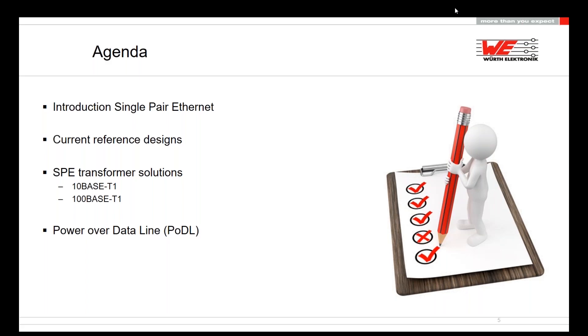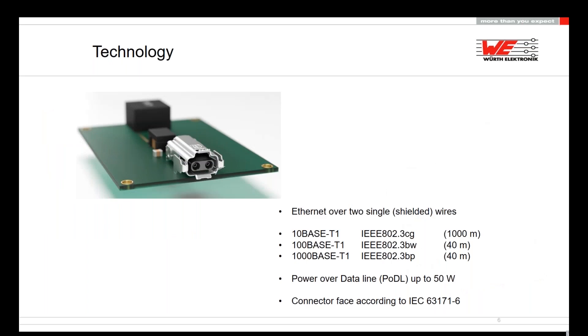Single-pair Ethernet is Ethernet over two single wires, as opposed to regular Ethernet over eight lines. These wires should be shielded in the industrial sector. We have three different norms: 10BASE-T1, 100BASE-T1 at 100 Mbps, and 1000BASE-T1. All these norms are defined in IEEE 802.3. Most interesting for the industrial field is 10BASE-T1, because you can reach 1,000 meters of cable length — useful for field buses, sensors, or cameras. The other standards are of course interesting for higher speeds.